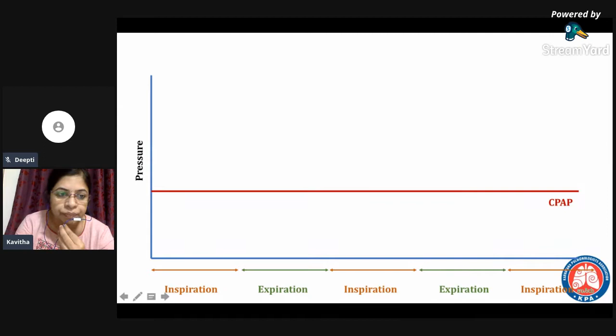We will not go into too much detail of the ventilatory aspects, but whatever basics you need to know, I'll be covering. So as you can see, this is the pressure and this is the breathing, that is inspiration and expiration. In a normal CPAP, that is continuous positive airway pressure, the airway pressure throughout the inspiration and the expiration will remain at the same level. Suppose I set a CPAP of 8 or 10 centimeters. Throughout inspiration and expiration, there is no change in the pressure that the device is providing to the patient, and it will remain at 8 or 10 centimeters.